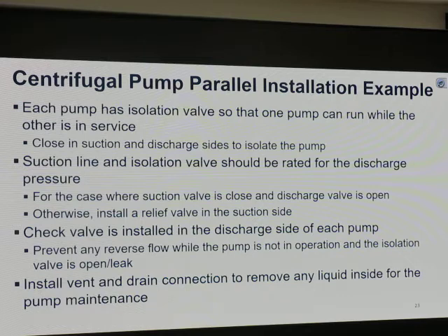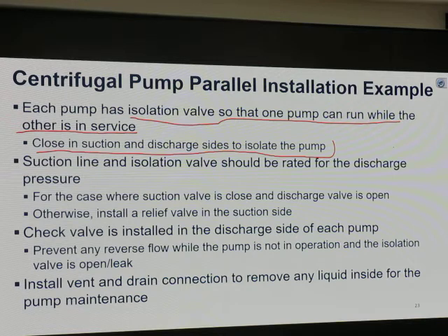Centrifugal pump parallel installation example. Each pump has an isolation valve so that one pump can run while the other is out of service. What is an isolation valve? What do you think? Joe, what is an isolation valve? Close the suction and discharge side to isolate the pump. That's the one. So basically we have the pump, and on the suction side and discharge side, we have a valve. We close those valves, then we can remove the pump, right? So I have two lines like this, with a valve over there and the pump in the middle. If pump number two needs repair, I can close that valve, and pump number one can still run. Okay, that's how we put them together.